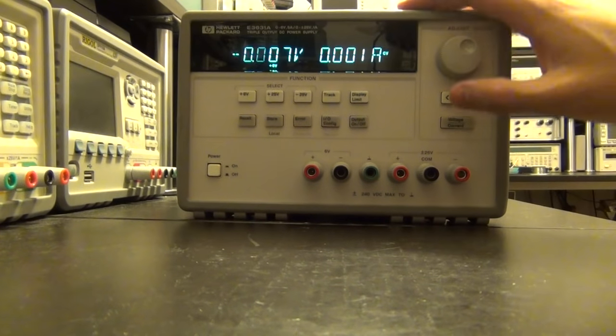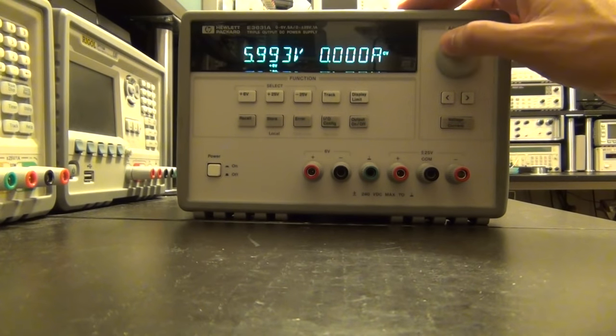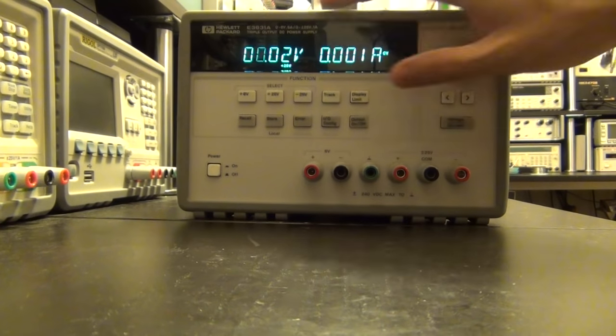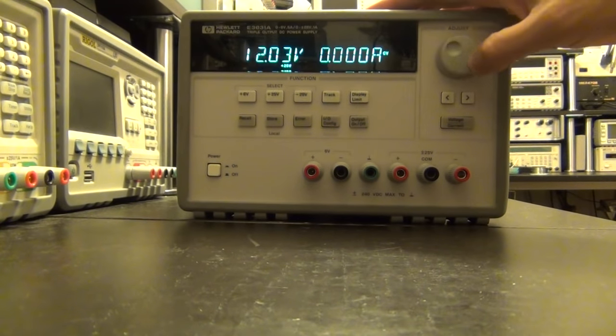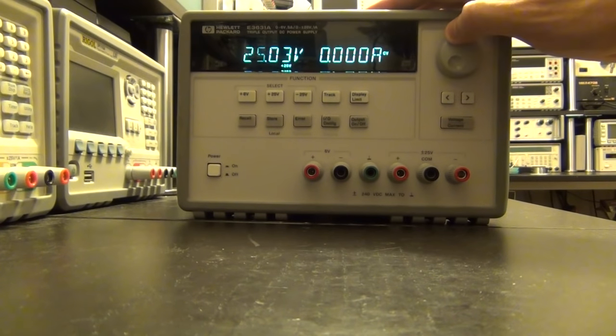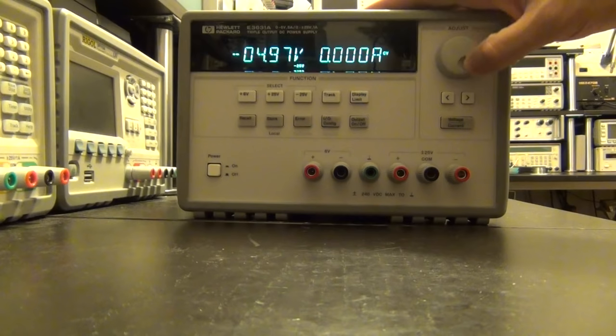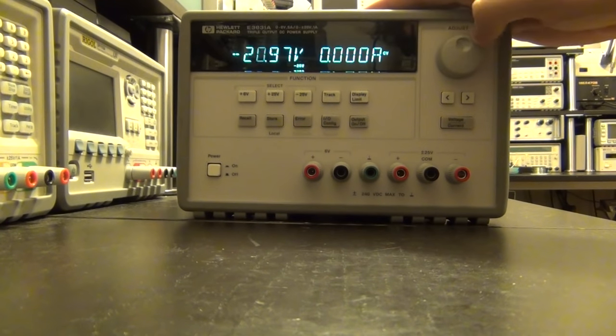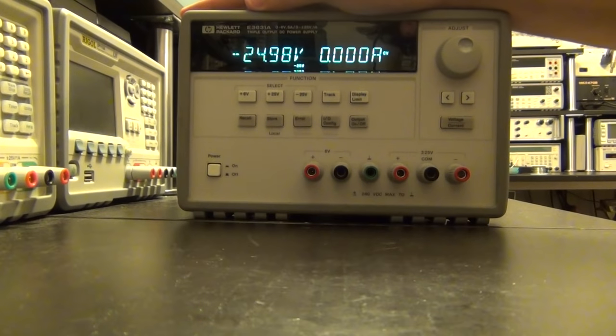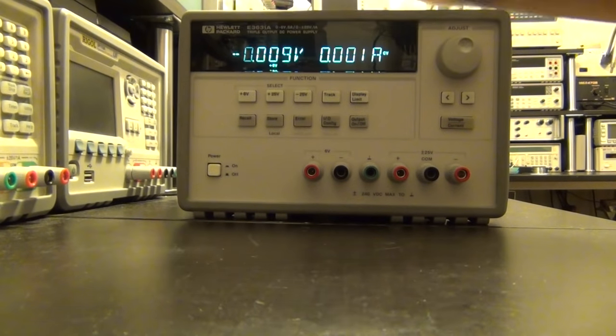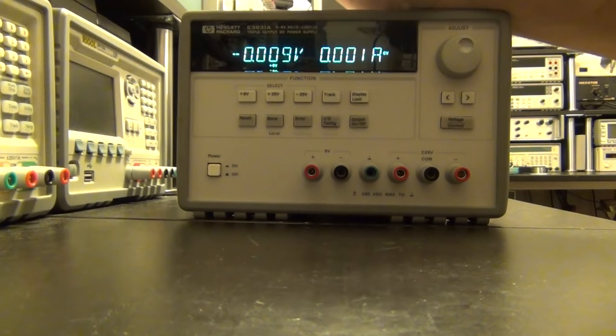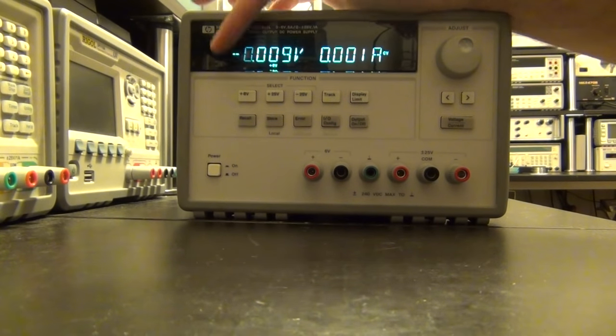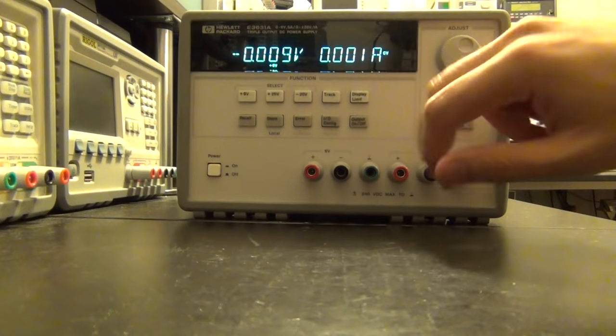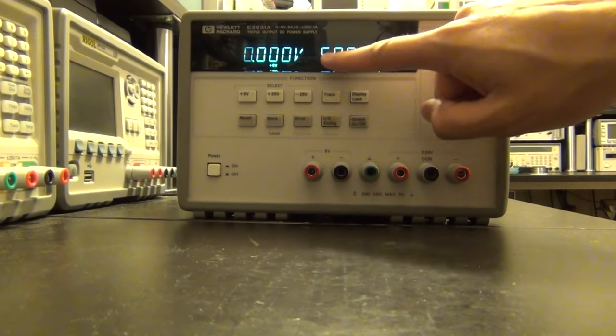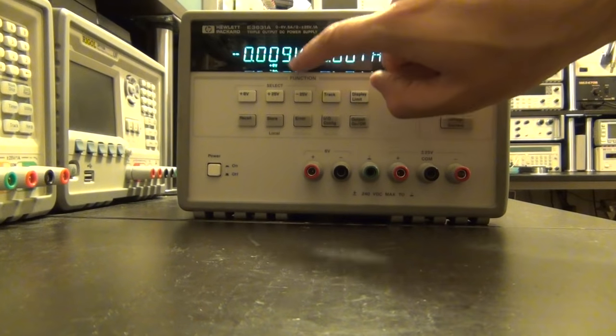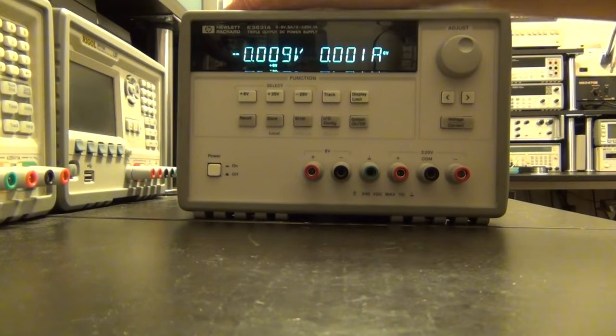Perfect. Turn it on. I can control the voltage. No problem. 25. You can see 25 volts, minus 25, and yep, seems pretty good. The only other thing I want to do is quickly verify how good the output voltage is versus what is displayed, because these power supplies measure what is actually at the output terminal, not what is being set. If I go on display limit, you can see that it is set to 0 volts, but if I turn it off, you can see it's measuring minus 9 millivolt.